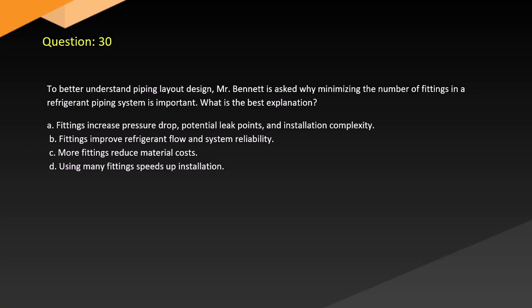Question 30. To better understand piping layout design, Mr. Bennett is asked why minimizing the number of fittings in a refrigerant piping system is important. What is the best explanation? A. Fittings increase pressure drop, potential leak points, and installation complexity. B. Fittings improve refrigerant flow and system reliability. C. More fittings reduce material costs. D. Using many fittings speeds up installation.